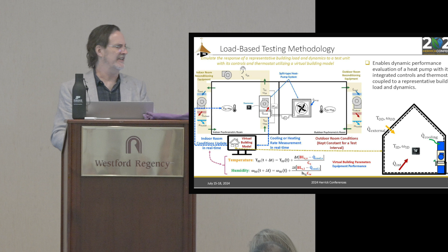condition. And so we've got 5 test conditions in cooling and 6 or 7 in heating, depending on the unit. And we get a whole bunch of test results, but the test results are lined up along that load line, and they include stuff like cycling and defrost that are separately accounted for in the DOE procedure mathematically, but not really in a real-life kind of way.